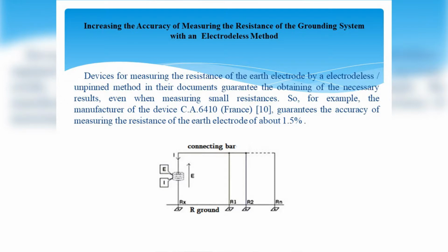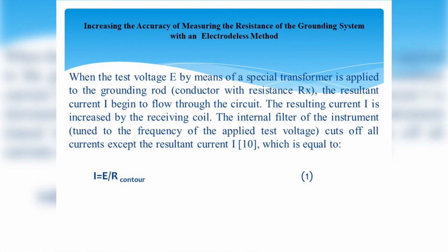For example, the manufacturer of the device CA6410 guarantees the accuracy of measuring the resistance of the earth electrode of about 1.5%. See figure. To create a closed electrical circuit the developers propose to use the neutral wire and neutral ground of the supply transformer. It is assumed to use a powerful supply system with a dead grounded neutral, in which the resistance of the neutral wire and the ground contour of the transformer neutral can be neglected. When the test voltage E by means of a special transformer is applied to the grounding rod conductor, whose resistance is Rx, the resultant current I begins to flow through the circuit.